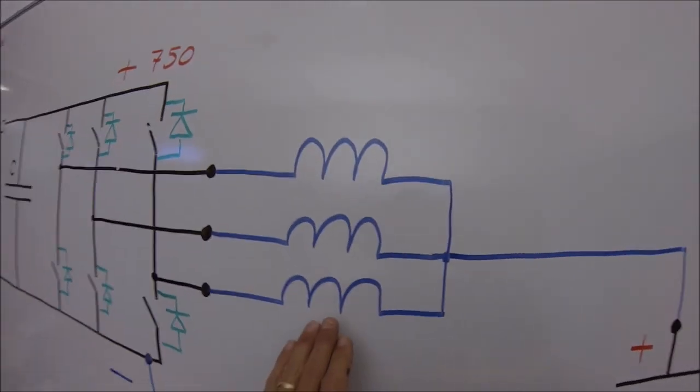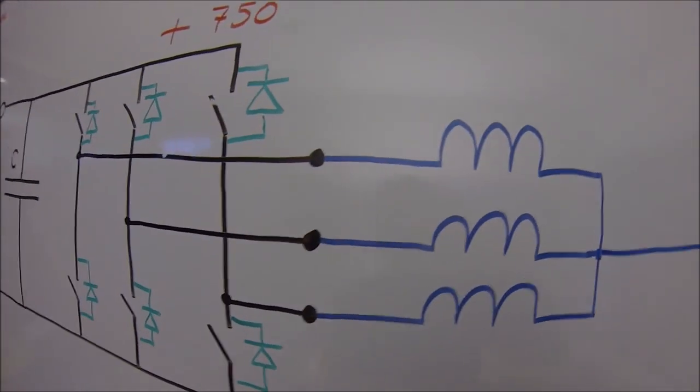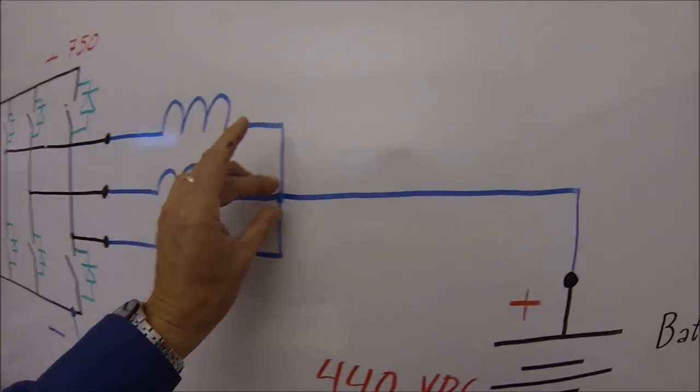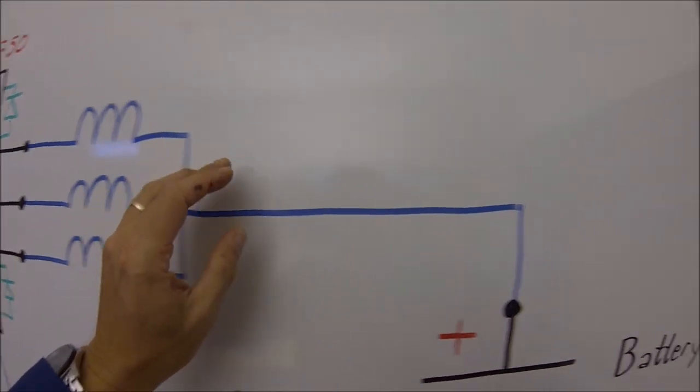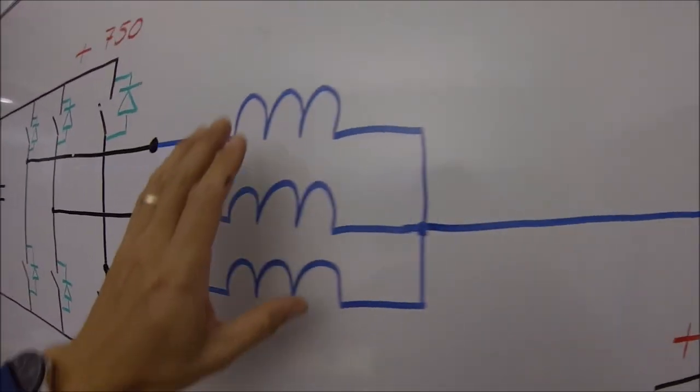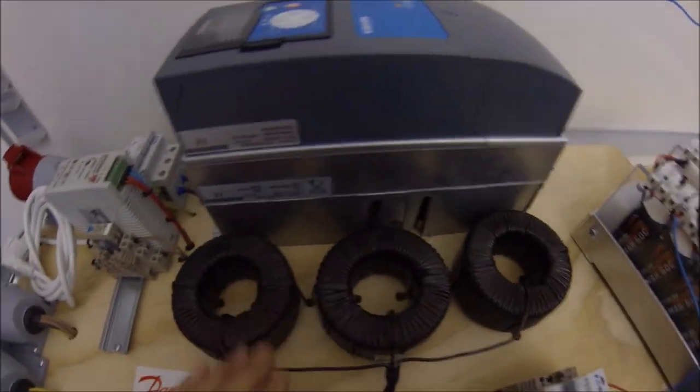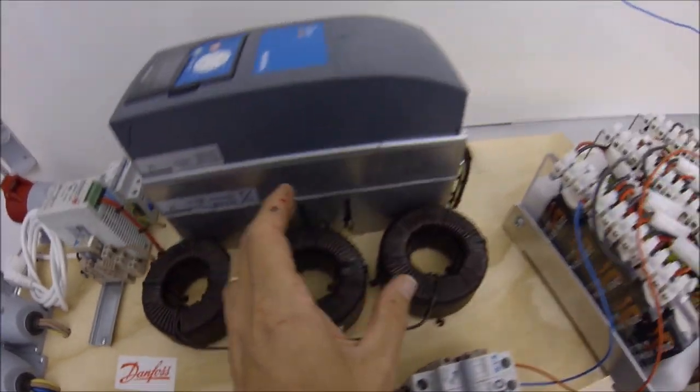We have to add these three chokes, one for each motor phase. They are connected together in one point and connected to the plus. It is important that these chokes don't have the same iron core. So this must be individual chokes.